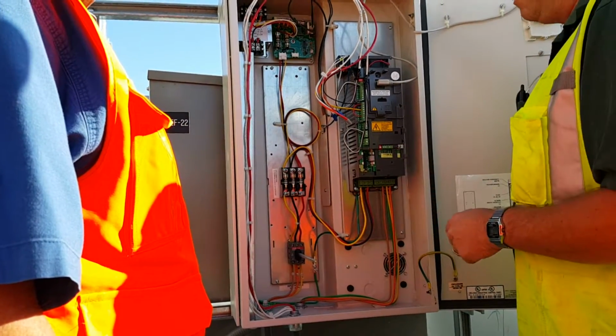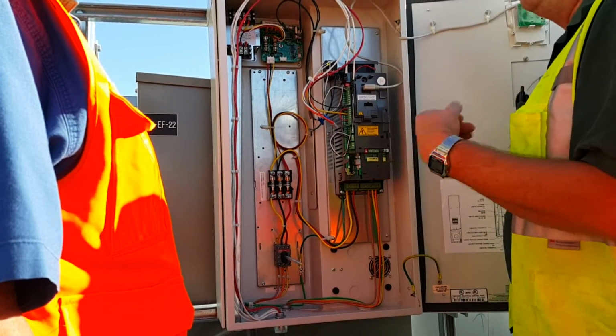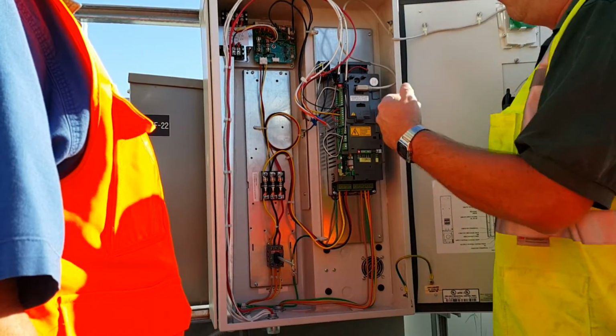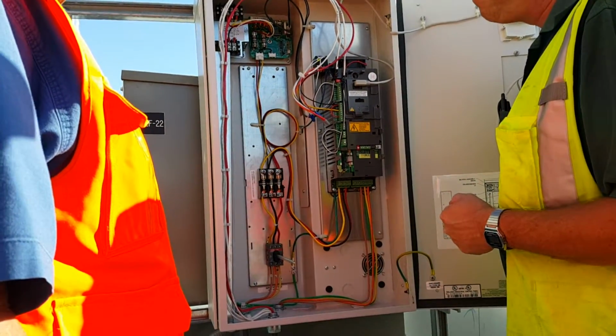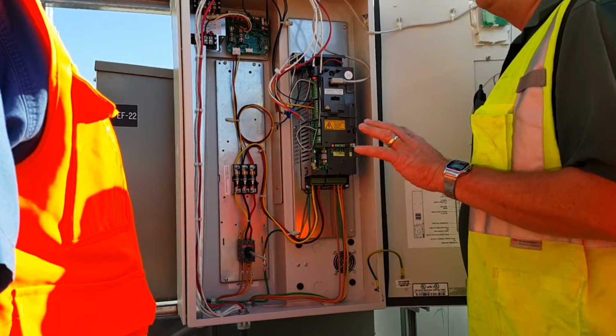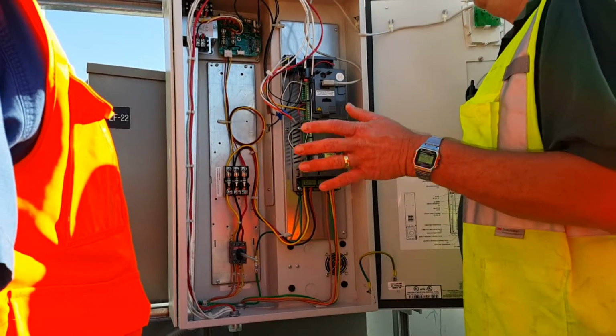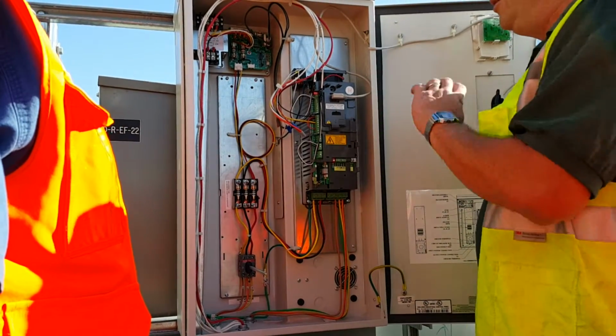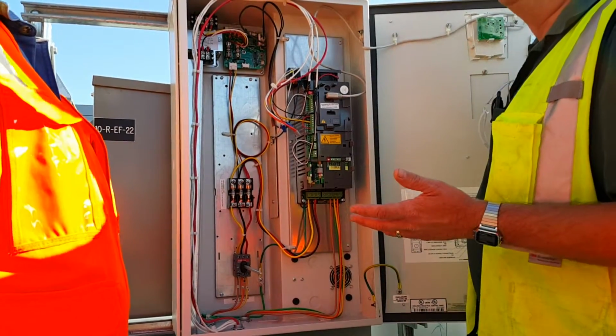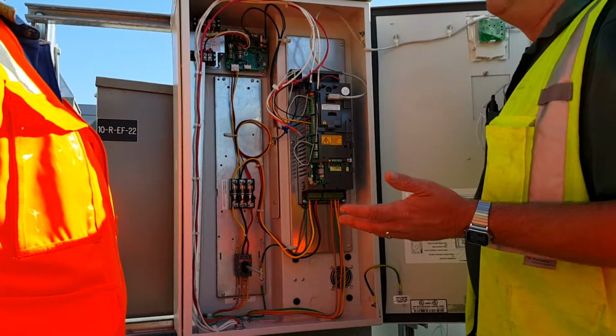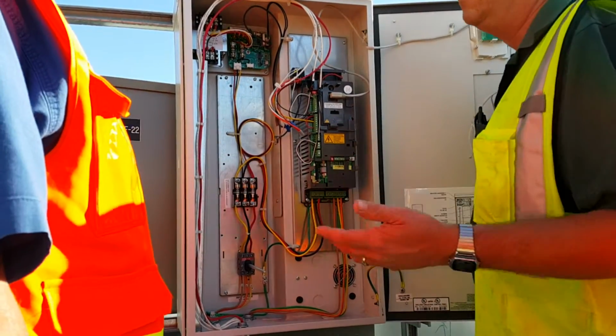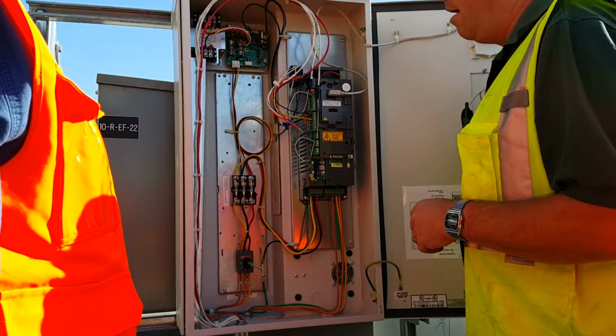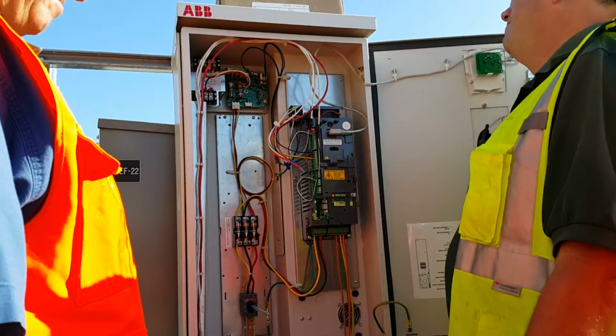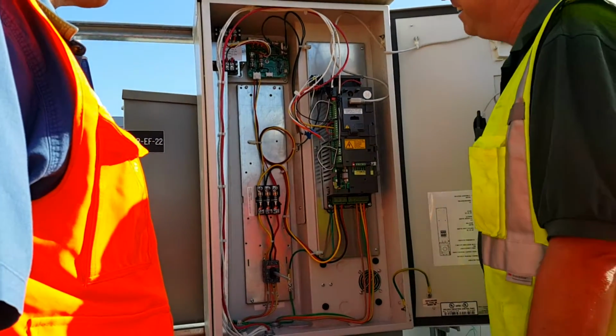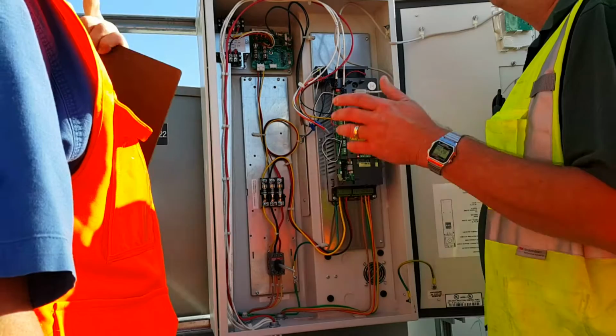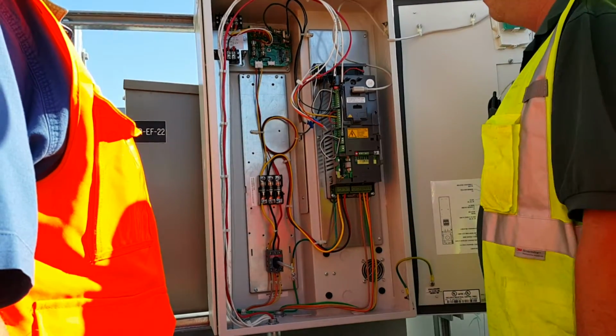There's a chance that one of the diodes on the rectifier shorted, that took it out. But all you do is clear that fuse. It's not too bad. But 2 or 3, you got something serious going on. I've been doing this for 22 years. I think twice I've had a case where we checked everything out, couldn't find anything, so what the hell, we put new fuses, and it came up and worked. And we never did know, something went across it somewhere and cleared, blew itself up. But that's 2 out of thousands of drives.